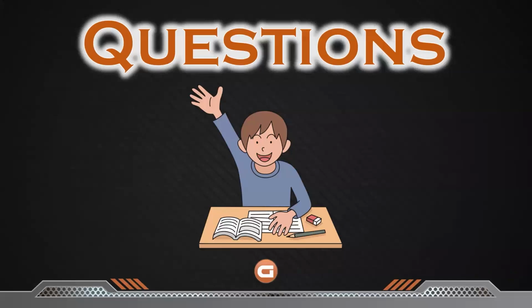Yes, Jim, I have told everyone in my training class, you get there in the morning with the job, you're going to install it. And I know everyone's got a lot of work and they can't afford to wait and send somebody back on a separate day to start this thing up. But if power is available and you get there in the morning and you set the outdoor unit and you tie the L1, L2 and get that power turned on, now it's crankcase heating and you can go run your line set. You can get the power run to the indoor head.